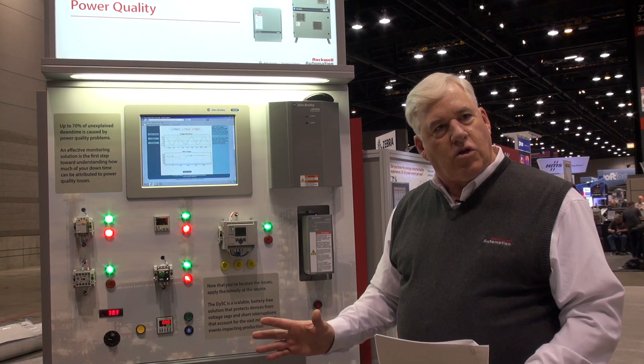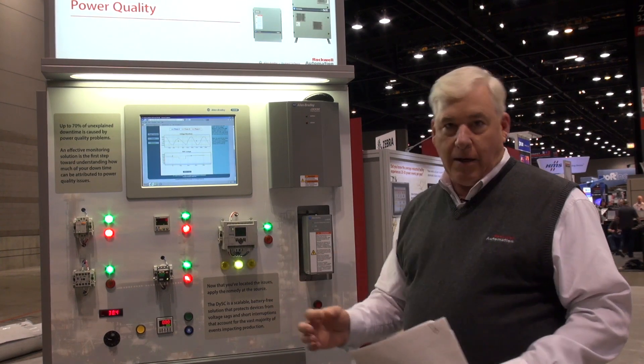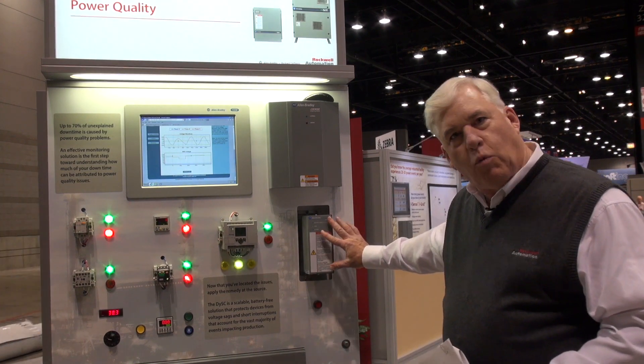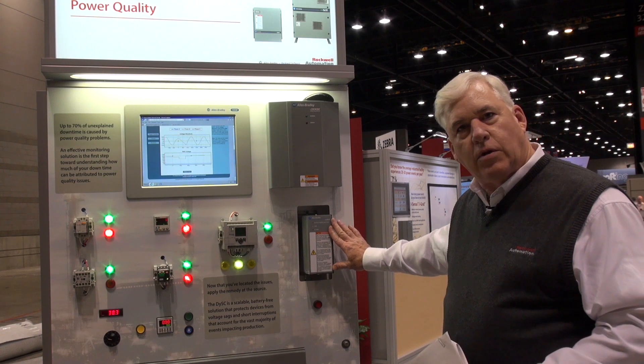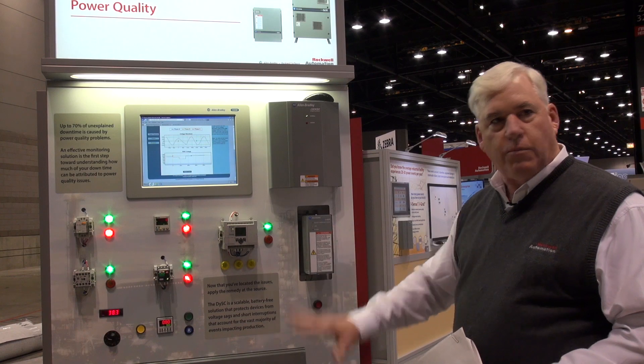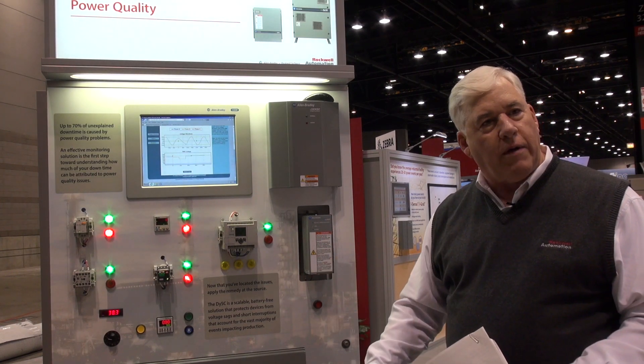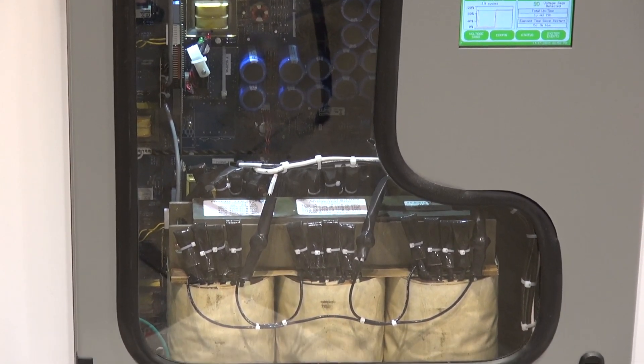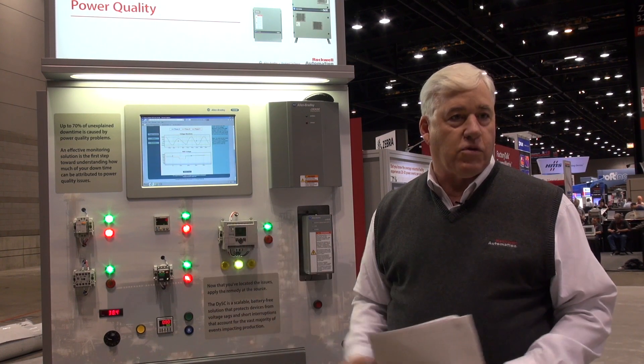Once that is understood, we can then take the next step, which is to correct the problem. Using patented products from Rockwell Automation, we can now correct that problem without batteries. These are products we call DySC — it stands for Dynamic SAG Corrector. They come in single phase products like this one from 2 amps to 50 amps, or three phase products that run all the way from 25 amps to 2,400 amps, making it possible to protect a machine, a bus, or the entire facility.